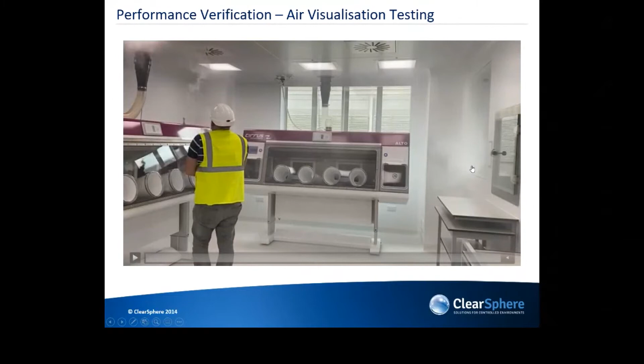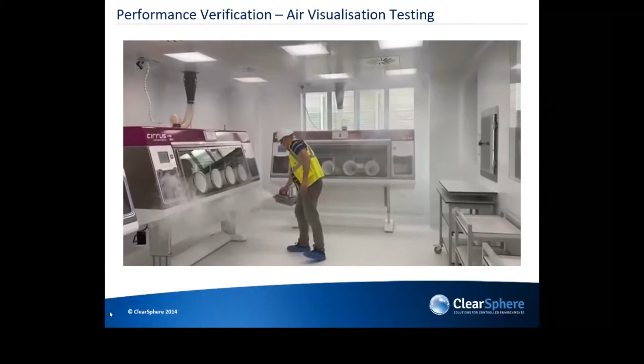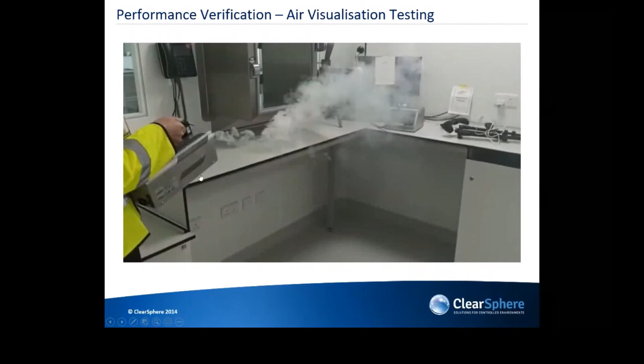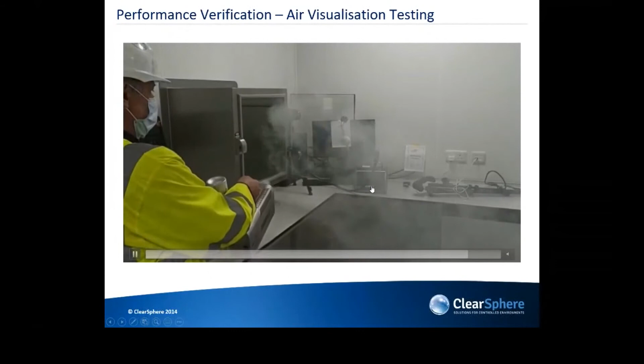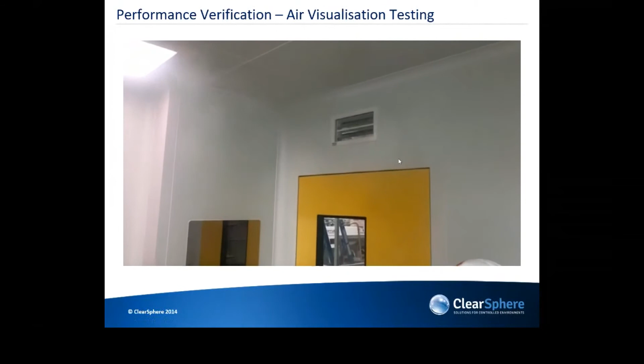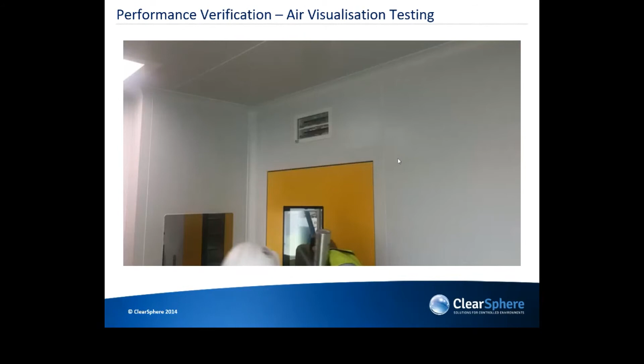The room visualization - we carried out visualization and recorded it. You can see one of the engineers demonstrating in around the isolators to make sure there's airflow throughout the entire room, around pass-through hatches. There's very good airflow happening there in around stabilizing dampers as well, so there's no dead spaces, and it would show up immediately if you did have dead spaces there.